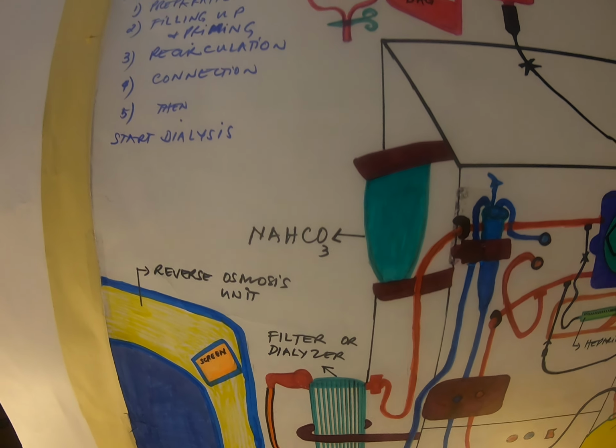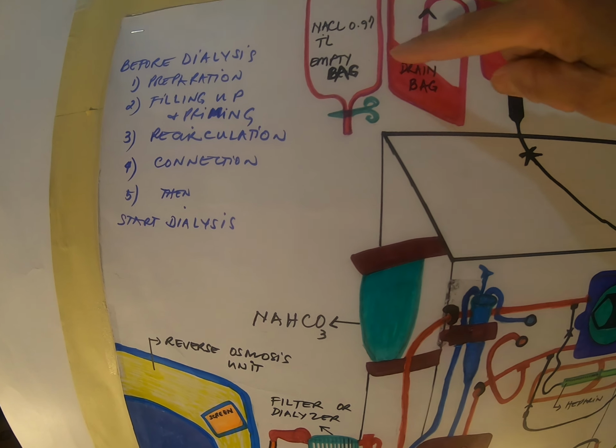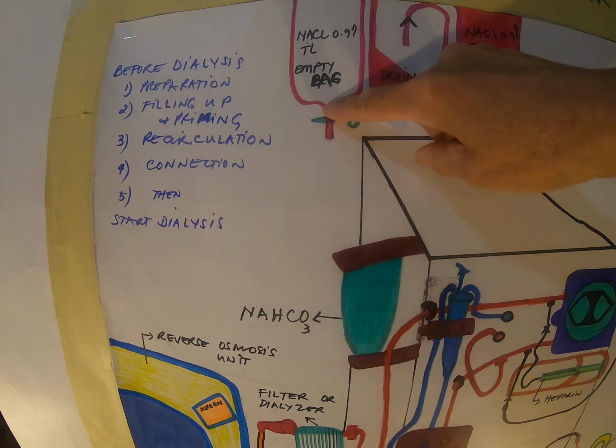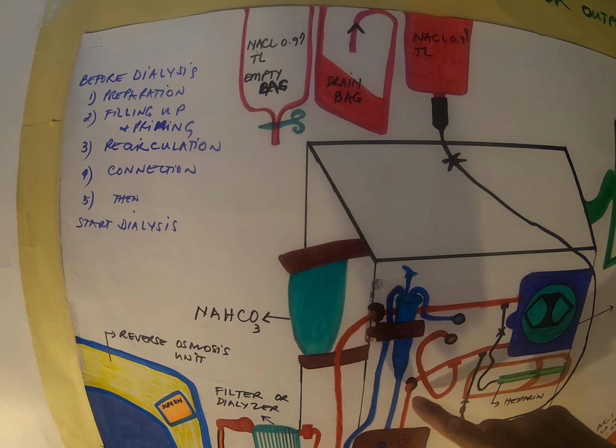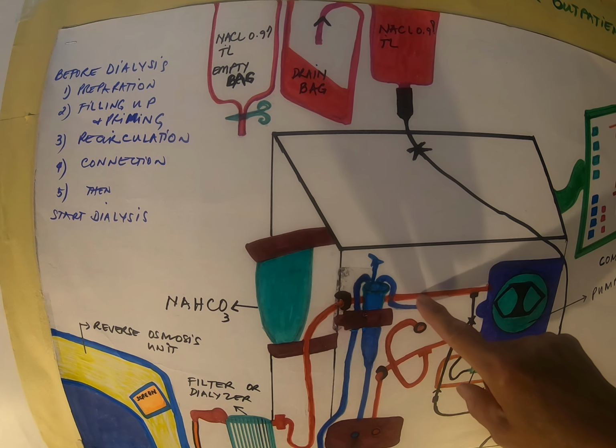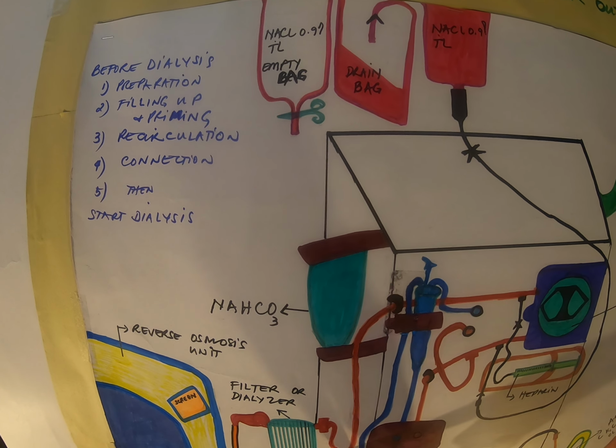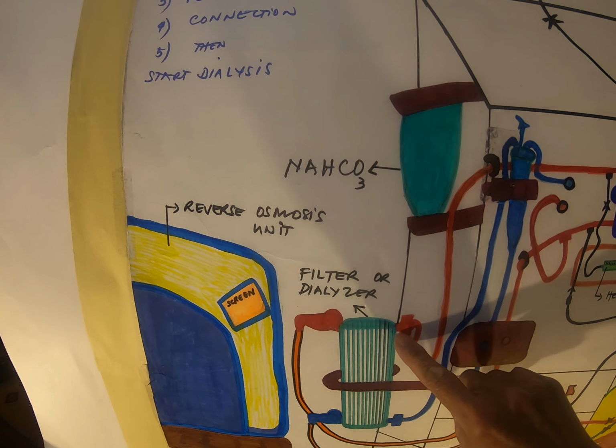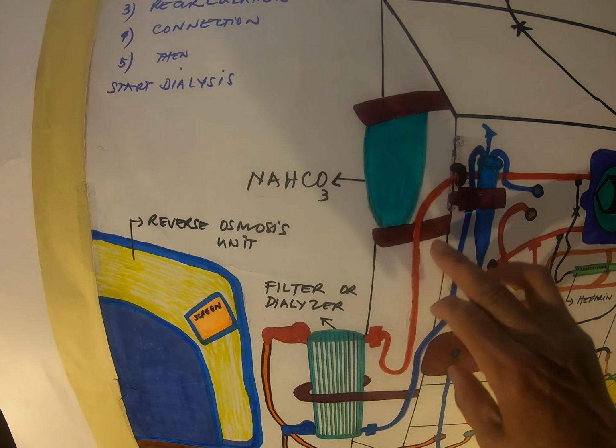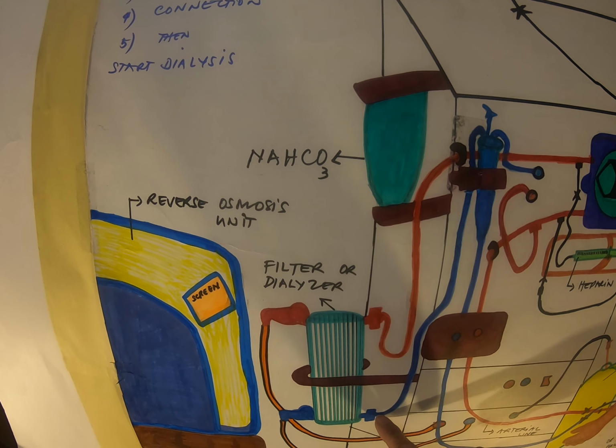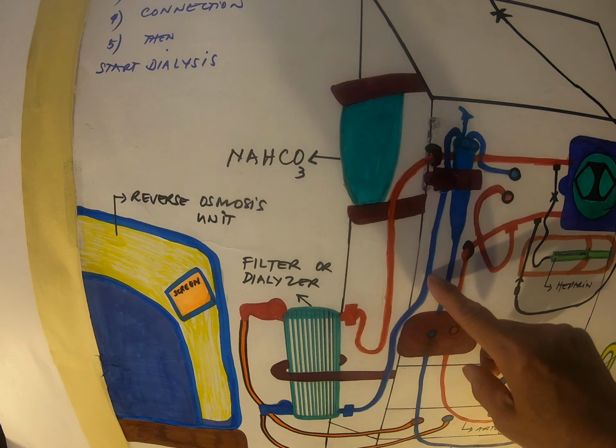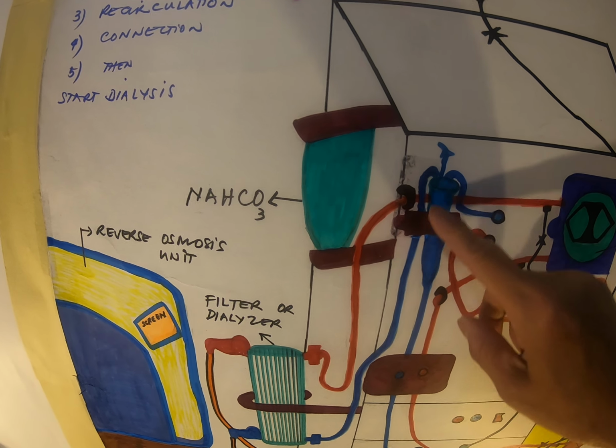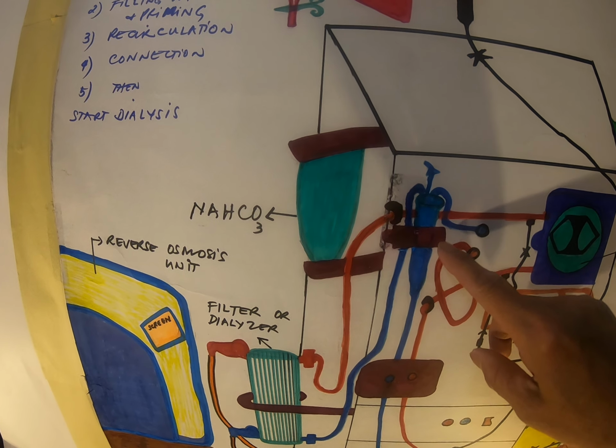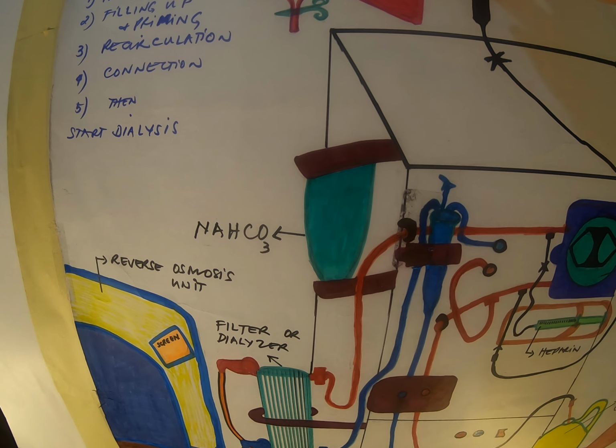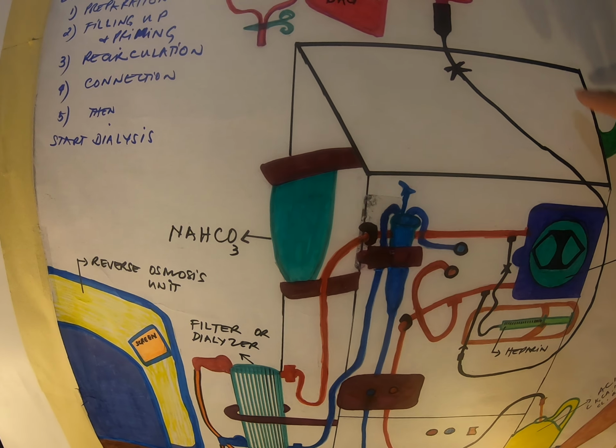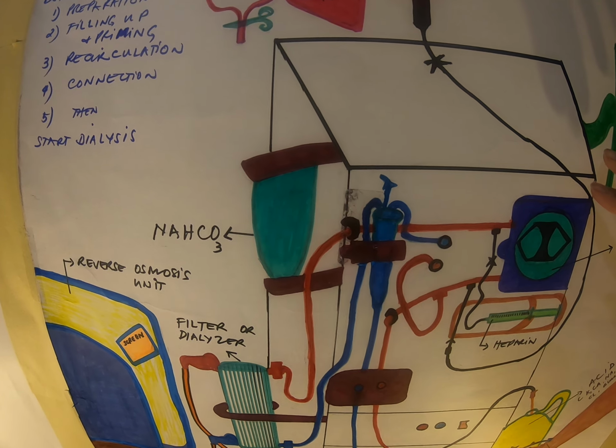So that's the filling up now. As this is opened, that is where the arterial line is connected. So the fluid gets in, and you notice air and everything in there. So fluid comes in, it goes to this dialyzer, which is in its final position before dialysis, but actually it is down. So it goes there, and then the fluid is picked up by this tubing. It goes to the chamber. More air will be trapped there, okay? And it goes to this drain bag, because we're not ready yet for hooking up the patient. And the heparin, as usual, is already primed. The sodium chloride remains clamped, okay? And I guess that's about it.